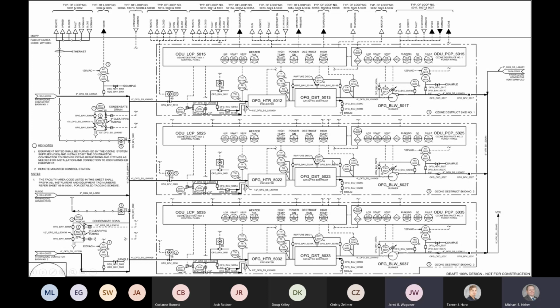Any instrumentation outside of those dashed boxes is procured by the electrical scope of work. On the left-hand side I'm seeing a couple of AITs, AEs, some pressure transmitters and temperature transmitters on the inlet or outlet side of these skids. They're not provided by the manufacturer, so they need to be picked up and tied in by the electrical scope of work.